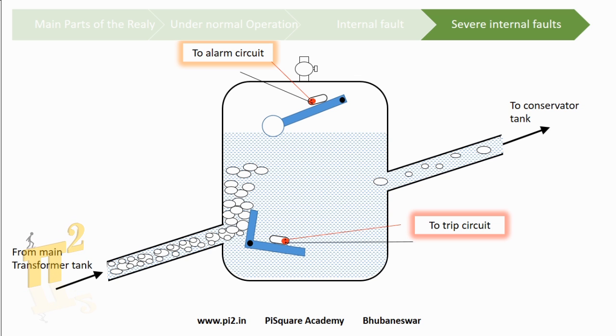The Buchholz relay protects the transformer from internal faults. As we see here, it can only work with oil-filled transformers, because only in oil-filled transformers can gases be generated.